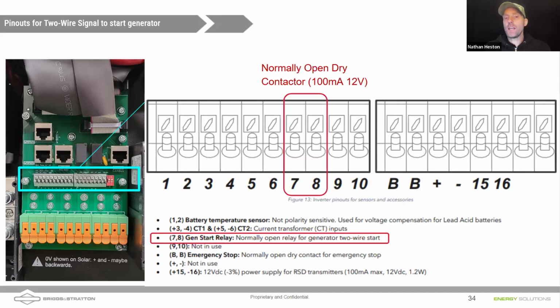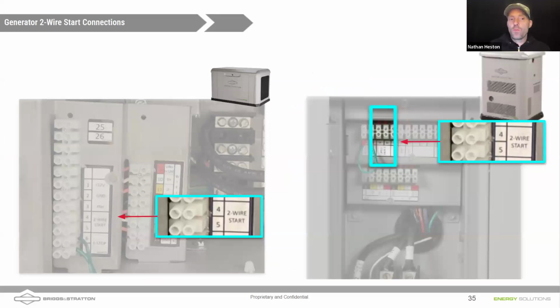Yeah, essentially pins 7 and 8 would be connected to each other by a relay inside the Sol-Ark, right? And so you need to have that source of voltage coming from outside. A dry contactor doesn't provide any voltage or current, it just closes those pins. And with a Briggs and Stratton generator, if you're using one of them, then it would be pins 4 and 5 for our controllers. I'm showing the 26K power protect on the left and a 13K on the right. Those pins 4 and 5 are the two-wire start. That's a normally open contactor, and when it's calling for two-wire signal to start on the Sol-Ark, it closes, and that will start up the generator.